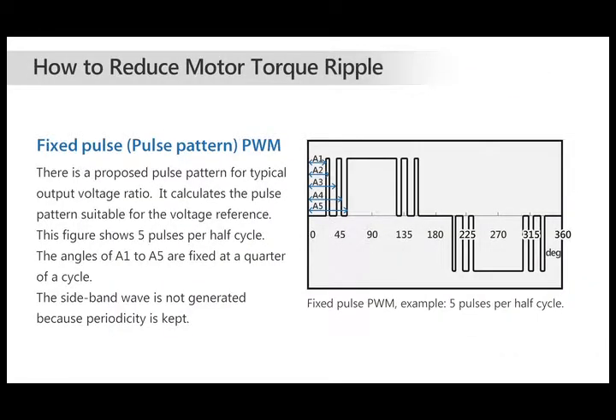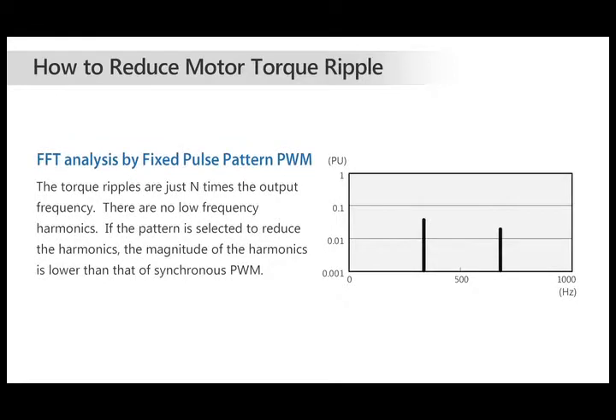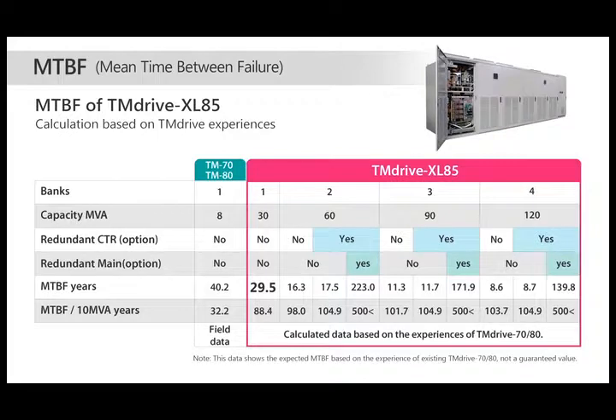As for the compressor drive, motor torque ripples can cause fatal torsional vibration. In order to avoid this issue, PWM control based on a fixed pulse pattern is applied for the TM Drive XL series drives as a standard feature. Sideband waves are not generated because PWM pattern periodicity is kept and symmetrical. The torque ripples are just n times the output frequency. There are no low-frequency harmonics. If the pattern is selected to reduce the harmonics, the magnitude of the harmonics is lower than that of synchronous PWM. The TM Drive XL series boasts a long MTBF of more than 20 years.